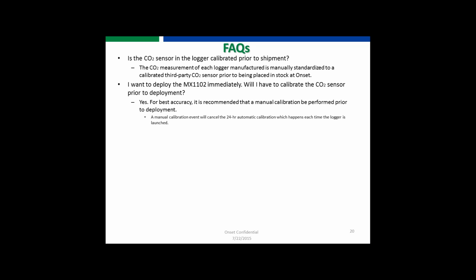And again, just a reminder, if you do a manual calibration, it will cancel that first 24-hour automatic calibration event. So you manually calibrate it, you put it in your space, and it'll sit there and log away. And then after 8 days, it will do its automatic calibration if you left that enabled when you launched it. Again, you have to launch the logger in order to use it and in order for it to calibrate. So you either have to launch it with your HOBO Mobile app or with the HOBOware app in order to use the device.